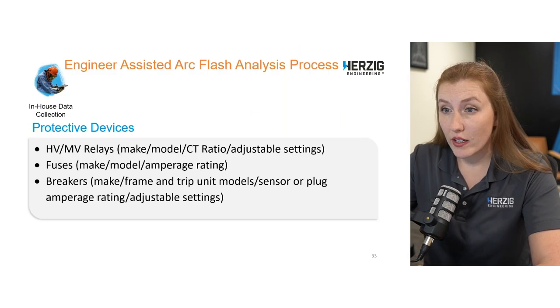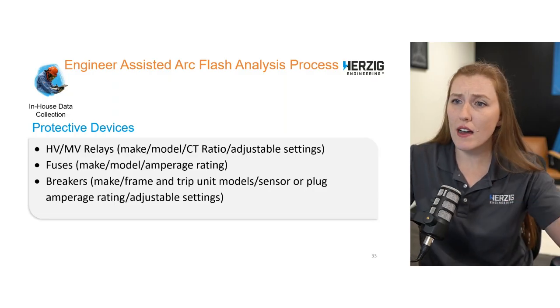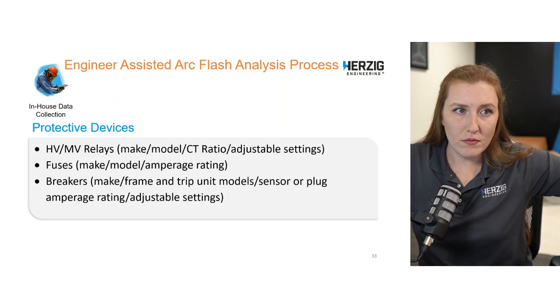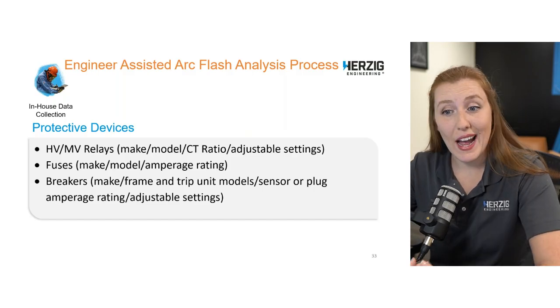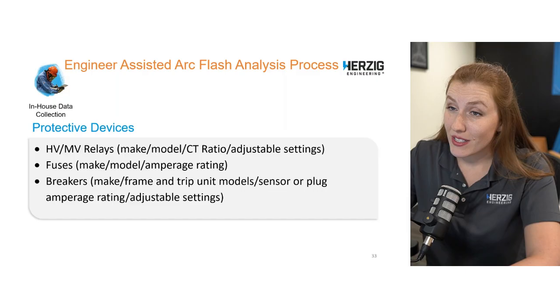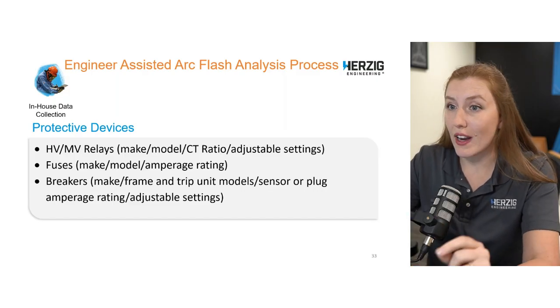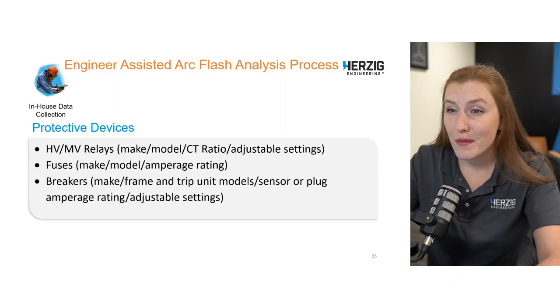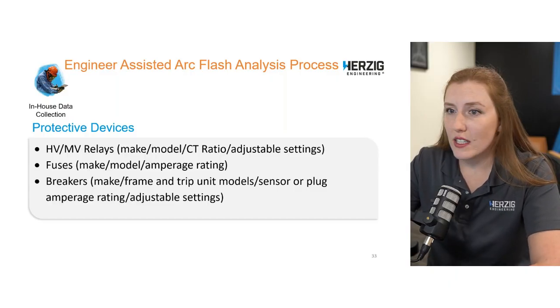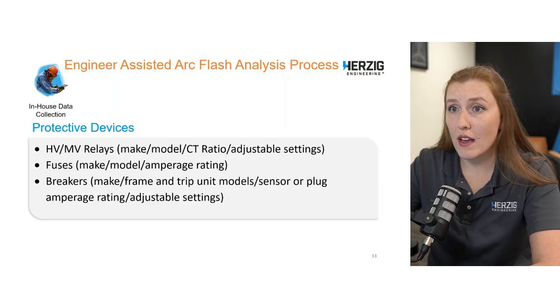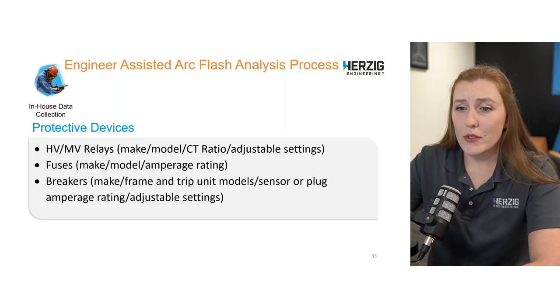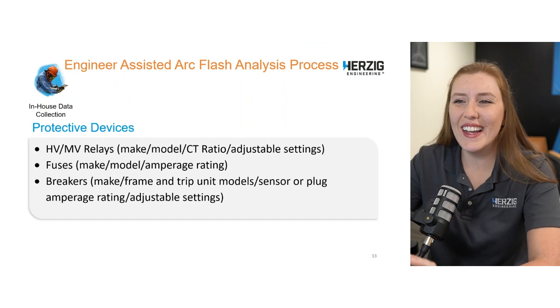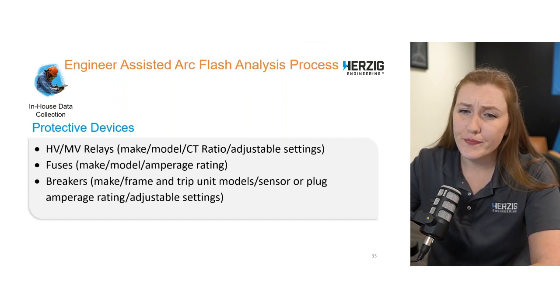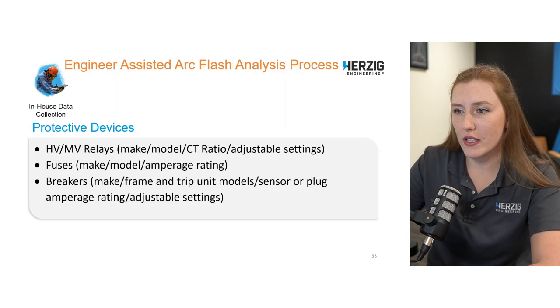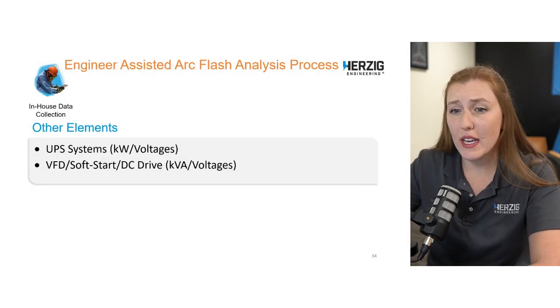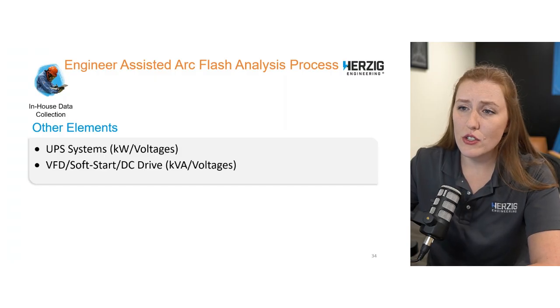Protective devices are a big part of it, and a lot of times people are like, oh yeah, we have this whole row of 200 amp breakers for this equipment, and it's like, I need the model, I need to know if there's adjustable settings and what every single one of them are set on for every single breaker. We want verification on all of them. For fuses, it's not just a 200 amp fuse, it's a 200 amp FRS-R fuse or an LPS-RK-SP or whatever. It's like we need all the details for breakers and relays and fuses, all those things. Other elements could be UPSs or soft starts or VFDs, DC drives, things like that.